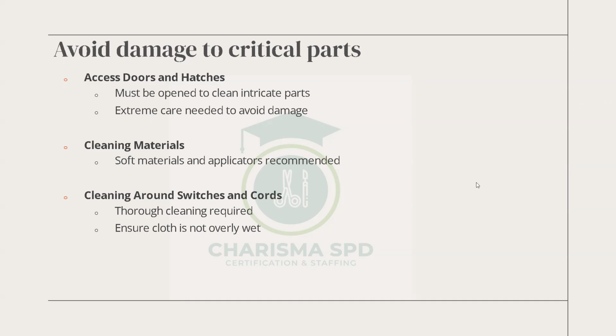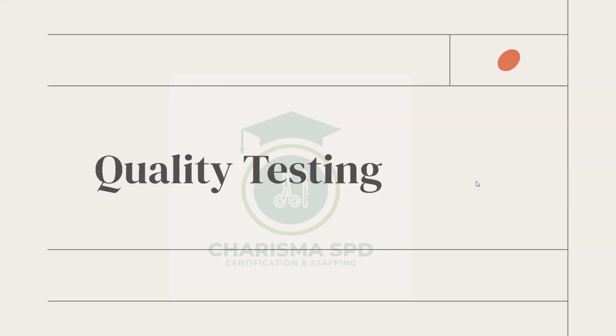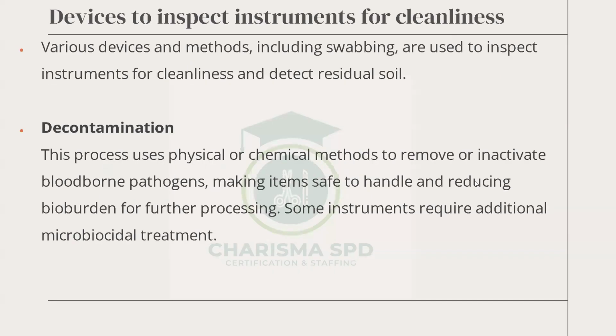And the next slide, Director. Quality testing. You know, we're all about quality, right? Devices to inspect instruments for cleaning. You have to make sure everything is clean. It's about cleanliness. Various devices and methods, including swabbing, are used to inspect instruments for cleanliness and detect residual soil. Like I told you about the fluorescent testing. You look at it under the fluorescent light and you see that, whoa, this was washed, but it still has protein on it. You need to check all that when the need arises to make sure the residual soil has been taken off.